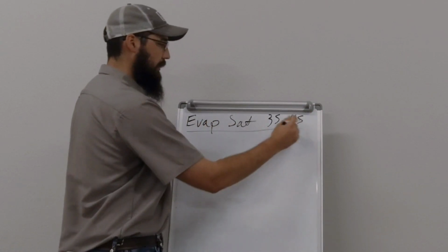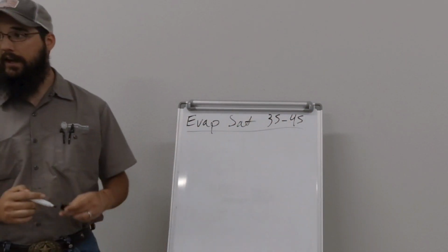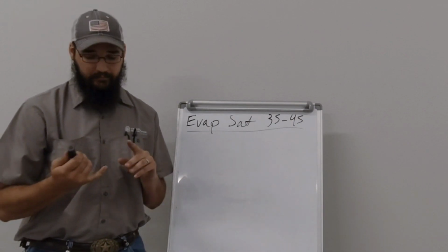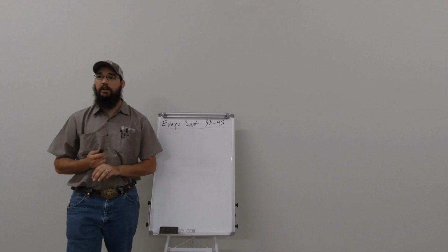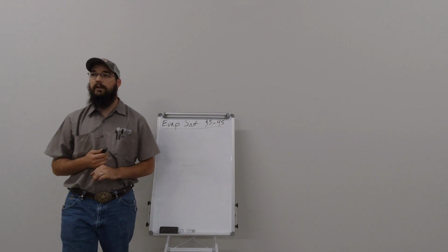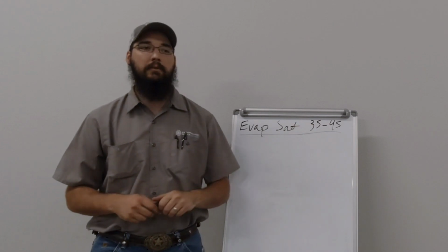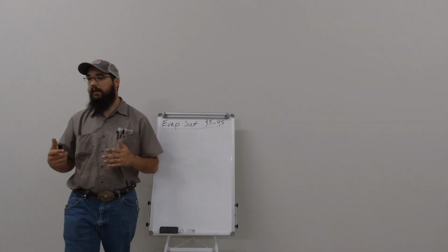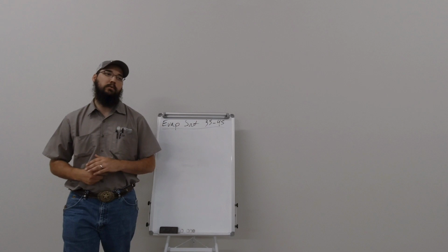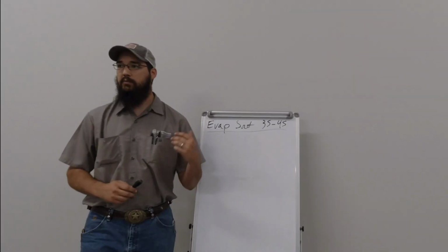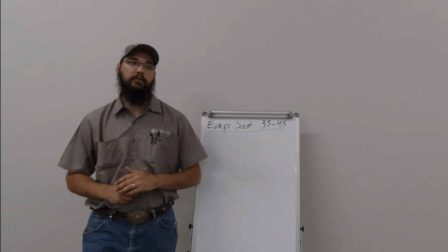Now, if I was to really do a deep dive on that, I would critique that even further. Honestly, by the time you start touching that 35, you've already got a problem somewhere. About the only thing that consistently might run 35 would be a system that's set up on a fixed board that's got a wide swinging load. The vast majority of the systems, I never want to see below 38.